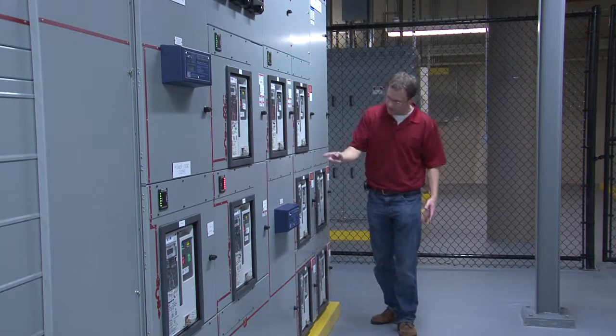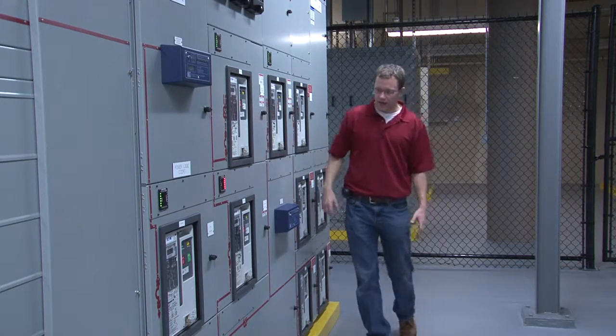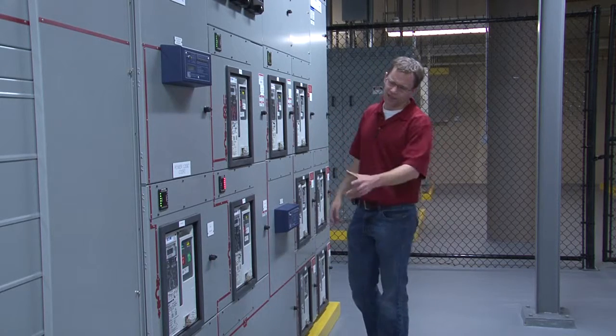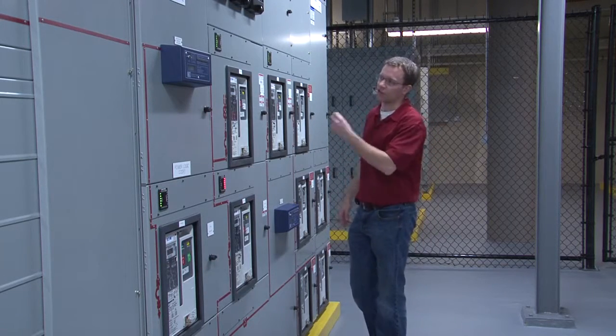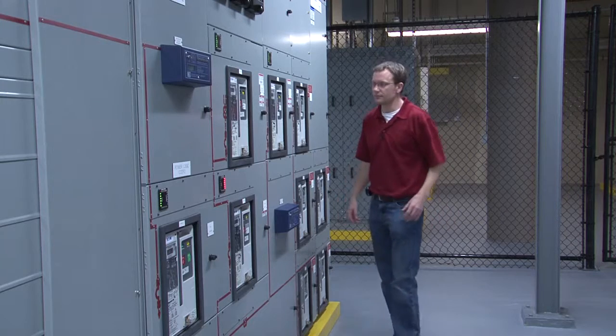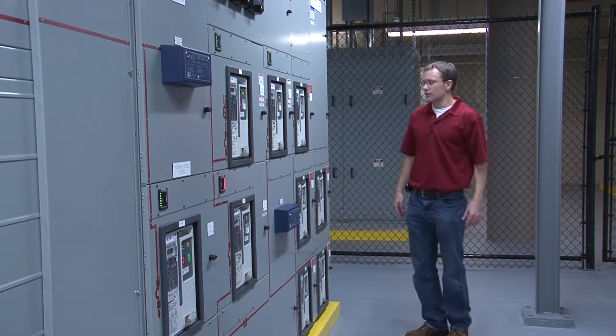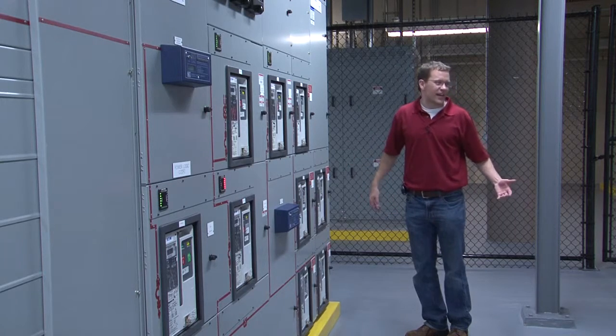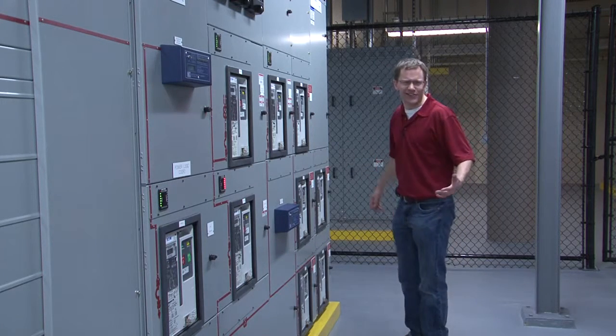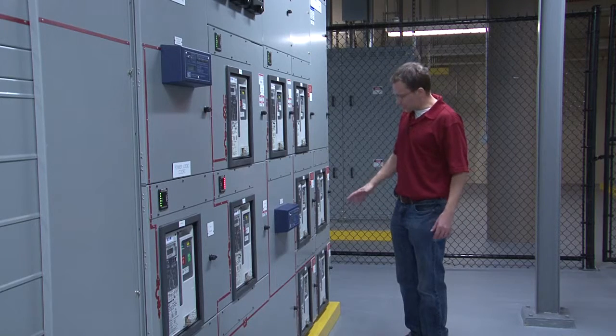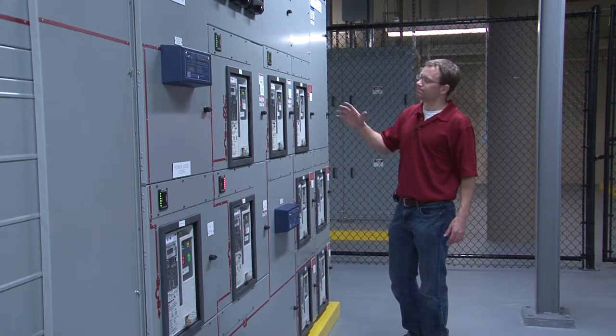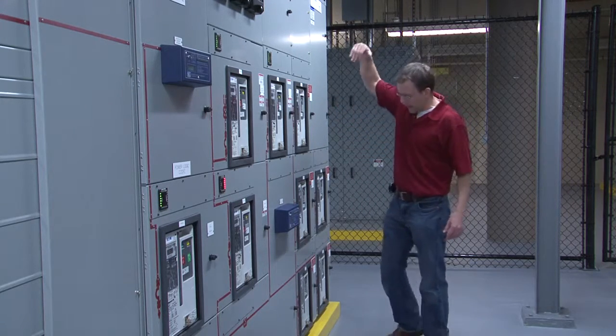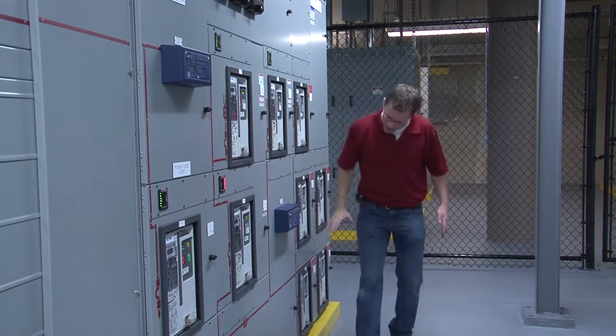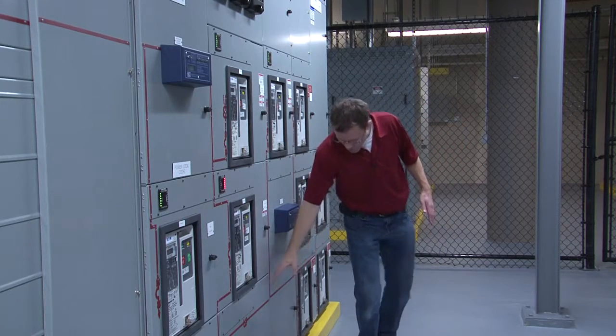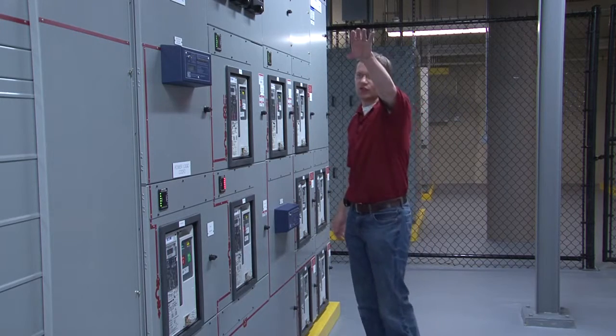1 from each UPS module, and then a 4,000 amp, or I guess 3,000 amp maintenance bypass breaker, which is right here. So it's not intuitively obvious that that's the case. So you just need to keep that in mind. So power flows into each of these breakers, hits this distribution bus here, and flows to the critical load.